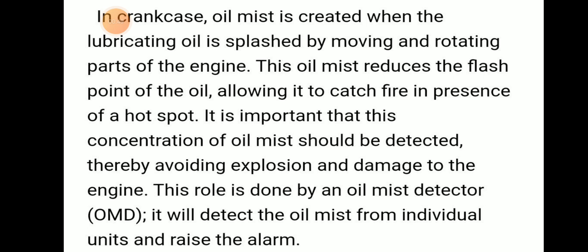Due to the moving and rotating parts of the engine, lubricating oil is splashed and oil mist is created. This oil mist will reduce the flash point of oil, allowing it to catch fire in the presence of a hot spot. So it is very important that the concentration of oil mist be detected. Thereby we can avoid explosion and damage to the engine. This role is done very nicely by the oil mist detector. It will detect oil mist from individual units and raise an alarm.